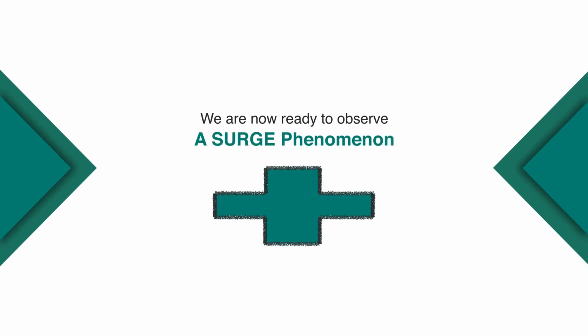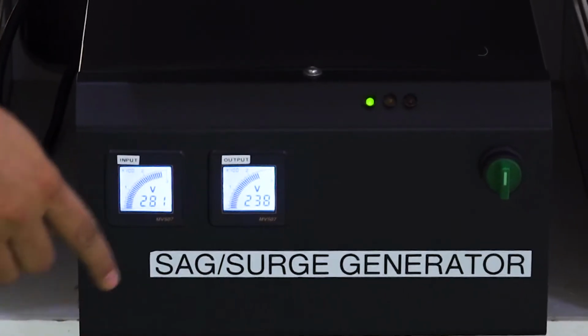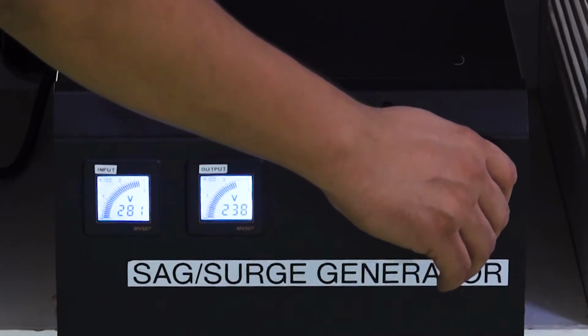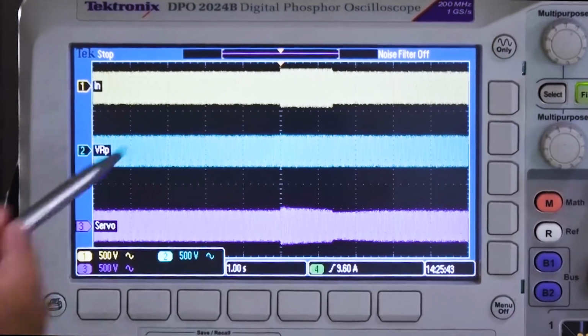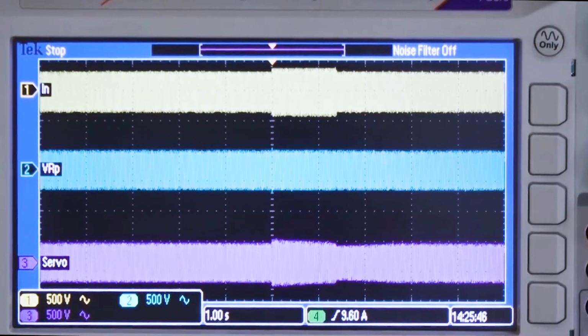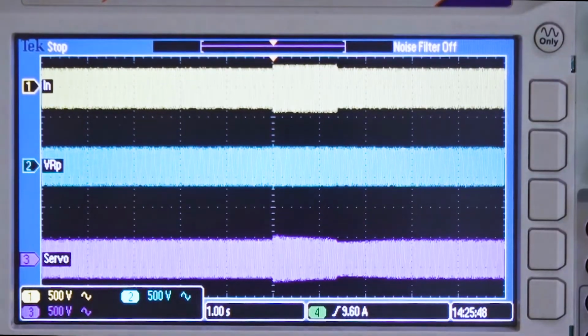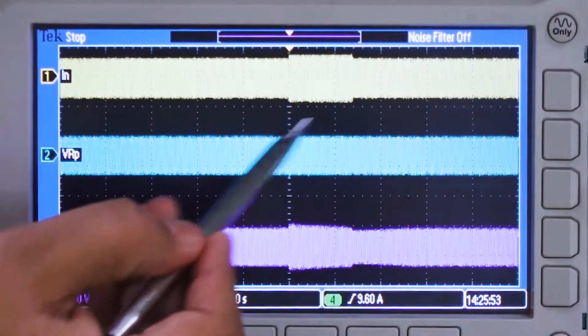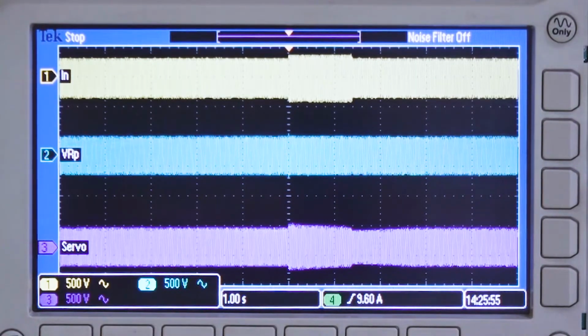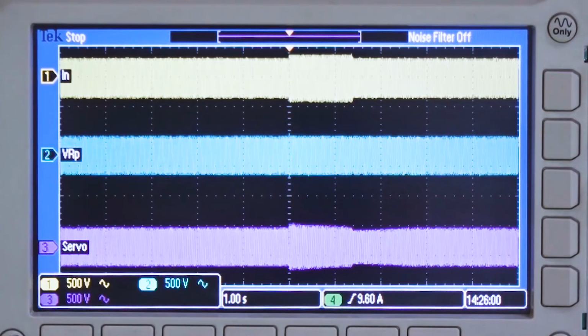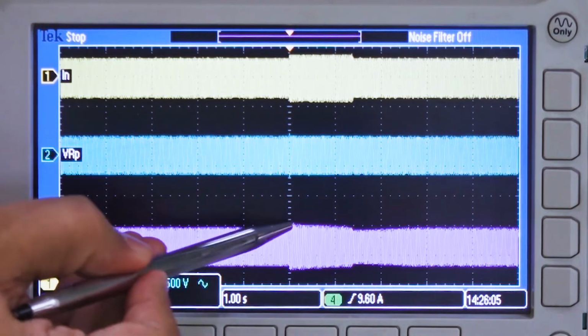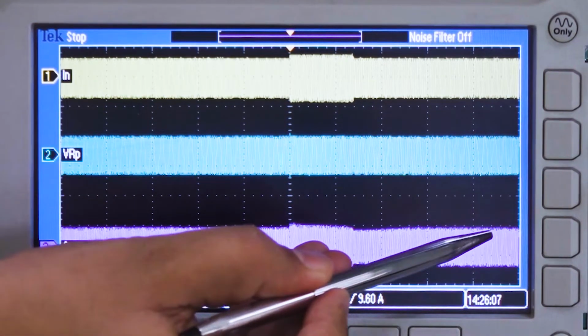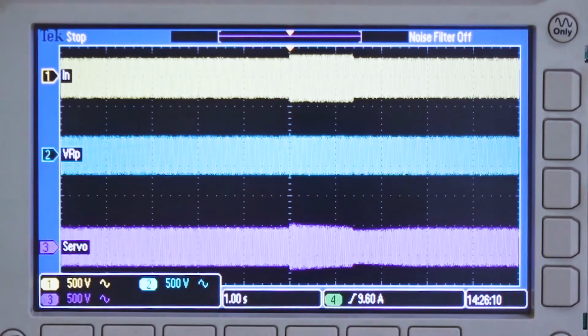Let's now observe a surge phenomenon. We will create a short duration surge of 20% magnitude and see the results. You can observe here, the topmost waveform is the input to the equipment, and this waveform clearly shows a surge. The second waveform is the output of the static voltage regulator, VRP, and you can observe the surge was corrected instantaneously. Whereas the third waveform is the output of the servo voltage stabilizer, where you will see that the surge was corrected slowly, and when the surge disappeared once again, the voltage was corrected back to its original value.